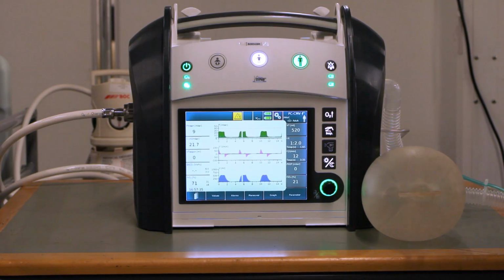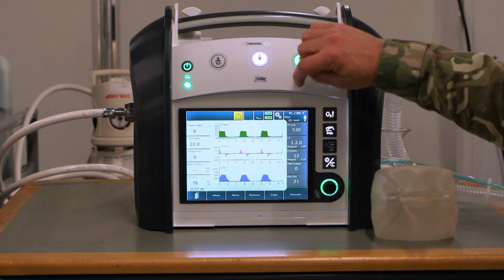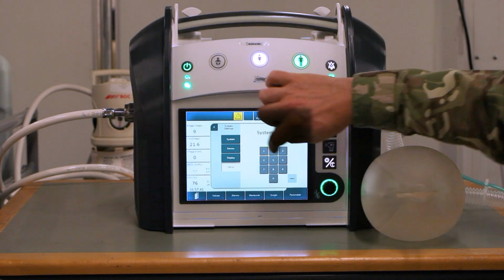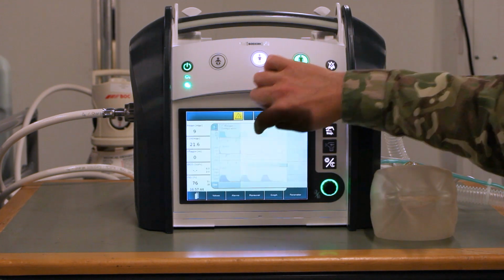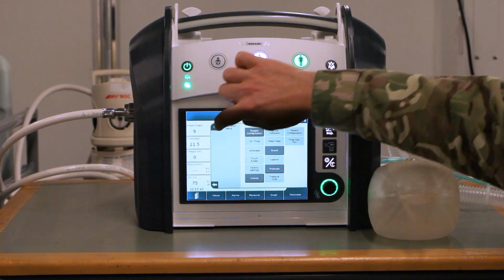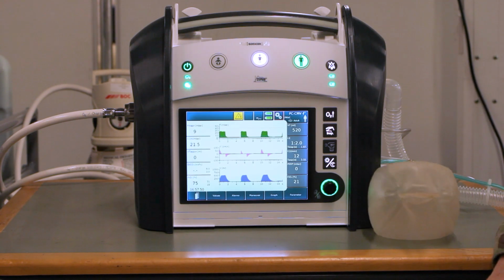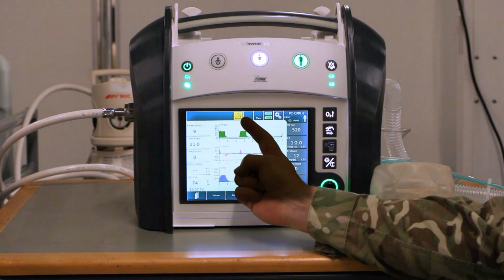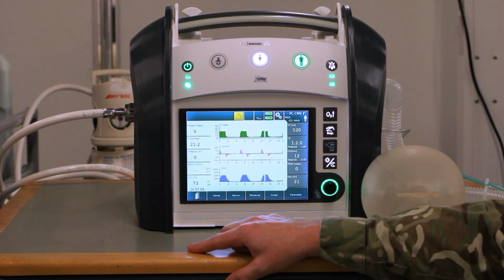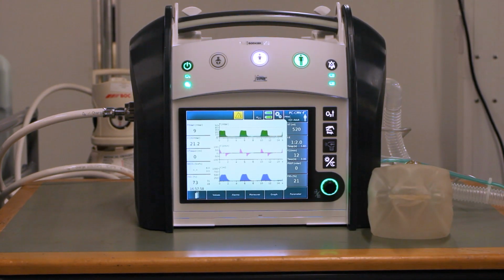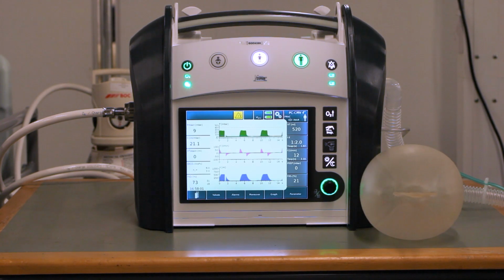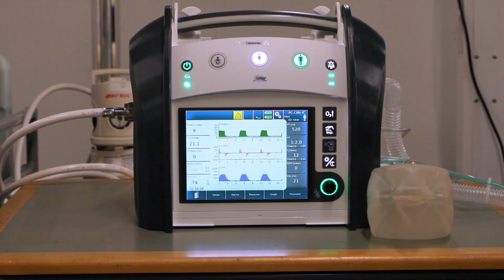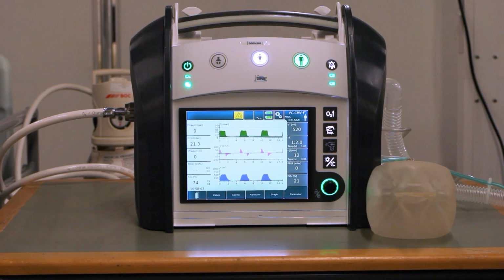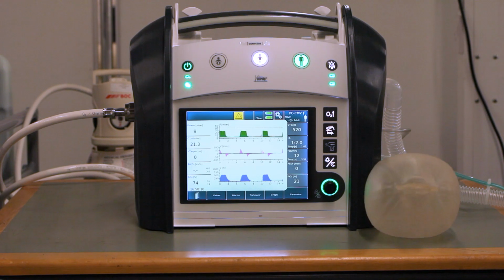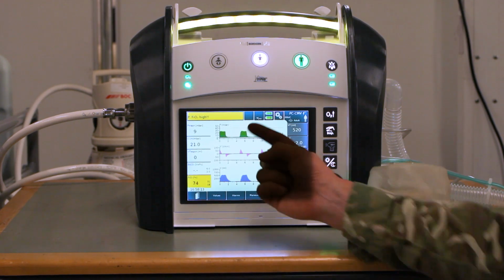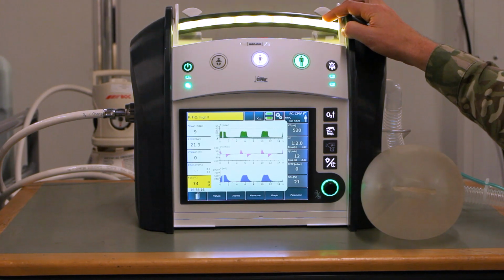If high pressure oxygen is still attached and the machine is told that it's in low pressure oxygen mode, then with high pressure oxygen still attached, what will occur is eventually you'll get a high FiO2 reading on alarm on this, because the FiO2 is now reading at 73%. This is just another indicator to ensure that you disconnect your high pressure oxygen and switch to low pressure oxygen delivered either via your oxygen concentrator or via your cylinder. Here is your alarm, and you can see it's alarming on the LEDs as well.